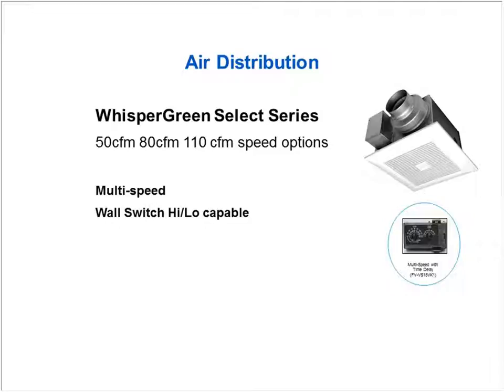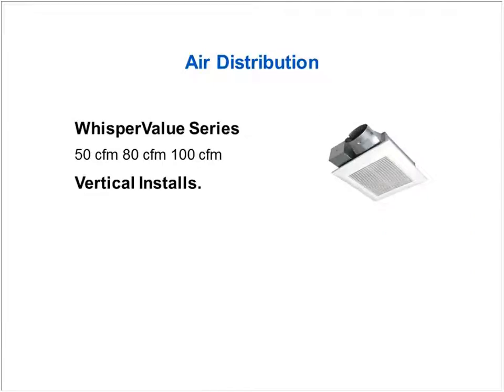So they like that. It's also got a high-low switch, so if I wanted more air in the other room, I can literally flip the switch, and now it'll go to the 50, 80, or 110 CFM value, and I can move more air. So that's one option. This is probably the most efficient option, most efficient energy-wise and least expensive. Option number 2 that we see is this Whisper Value.